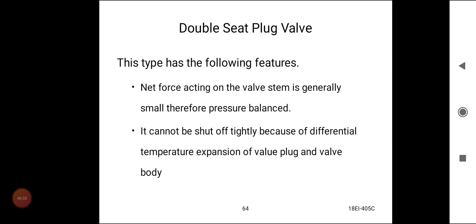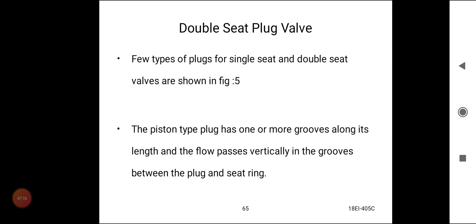The net force acting on the valve stem is generally small, therefore it is pressure balanced. It cannot be shut off tightly because of differential temperature expansion of the valve plug and valve body. A few types of plugs for single seat and double seat valves are shown in the figure. The piston type plug has one or more grooves along its length, and the flow passes vertically in the grooves between the plug and seat ring.